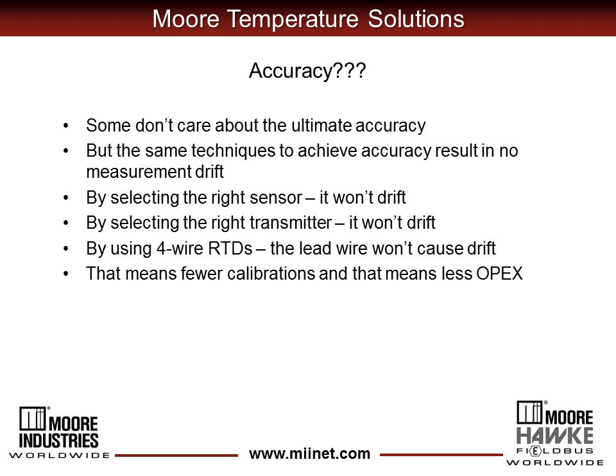Because the same techniques we use to achieve accuracy also achieve a more stable temperature measurement. Things like selecting the right sensor reduces drift. Selecting the right measuring instrument reduces drift. Using four-wire RTDs reduces drift caused by lead wire. And if you reduce drift, you push out the frequency of your calibrations and/or verifications, and that directly impacts operating expenses. So improving accuracy and reducing measurement drift can be related and can have measurable results.